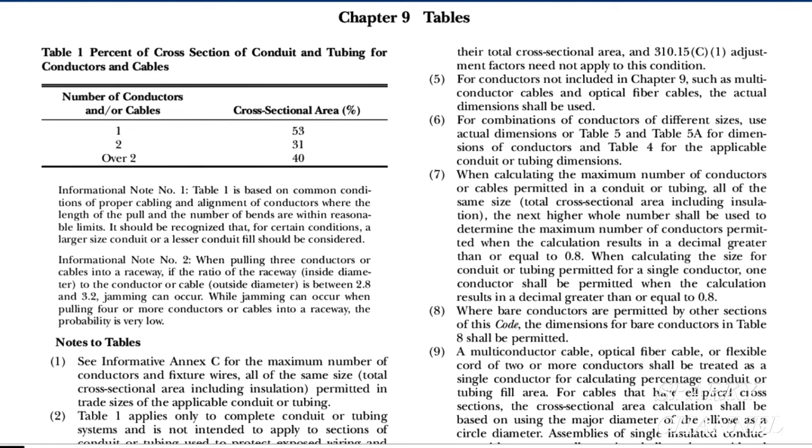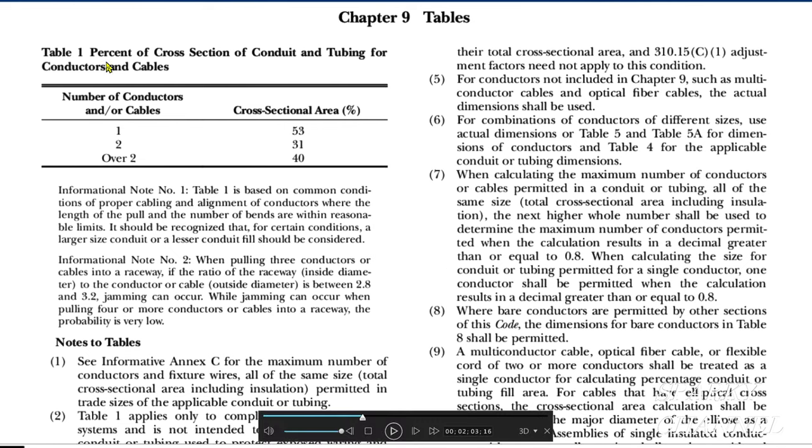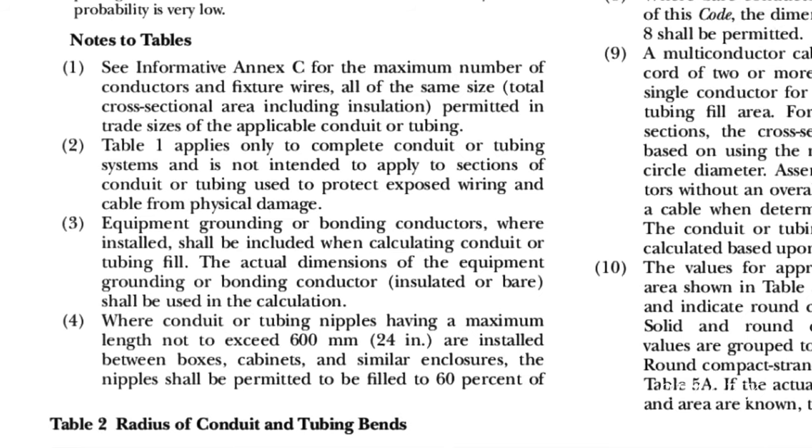So first, let's see if we should use that EGC wire in our EMT fill calculations. This is the 2020 NEC Code, Chapter 9 Tables, and Table 1 is percent of cross section of conduit and tubing for conductors and cables.